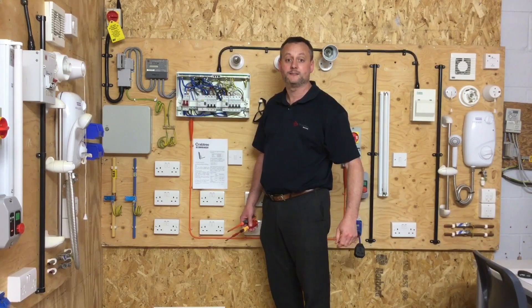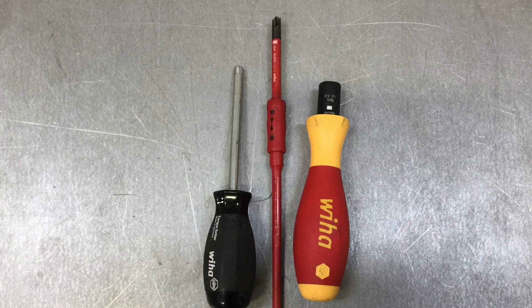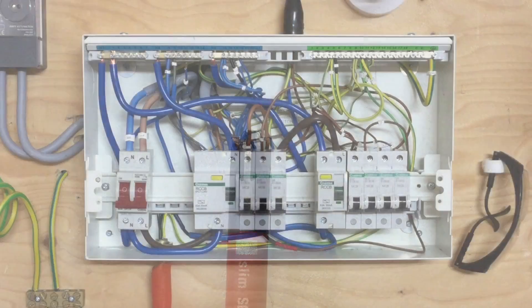We can see in the literature provided with the distribution board that the manufacturer has set the Newton meters of torque required for the main switch, the MCBs, and the earth and neutral terminals — and these are what we'll be using during this presentation. We will also require a calibrated torque screwdriver incorporating a plus-minus head, not a Pozidriv screwdriver head.